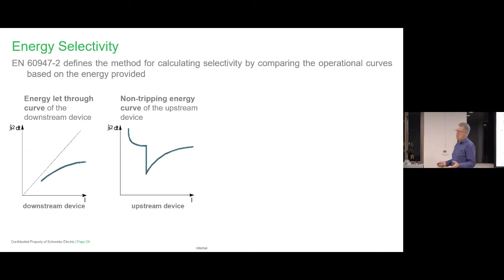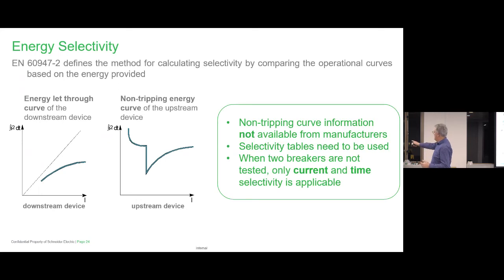We're able to determine it through the software anyway, what you need, and we're recommending this breaker with this breaker, as the coordination tables will tell you. But these are what the breakers are able to withstand under very high short circuit values, and we have curves for them. And, I'll just say over here, the selectivity tables must be tested. Going back to your question before, when two breakers are not tested, only current and time selectivity can be used.